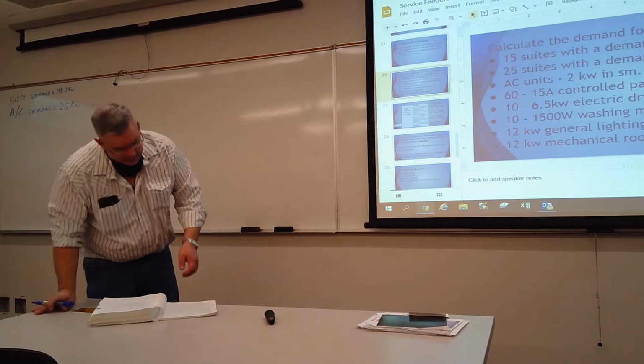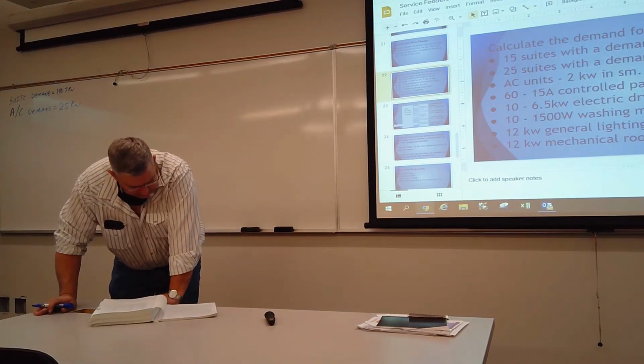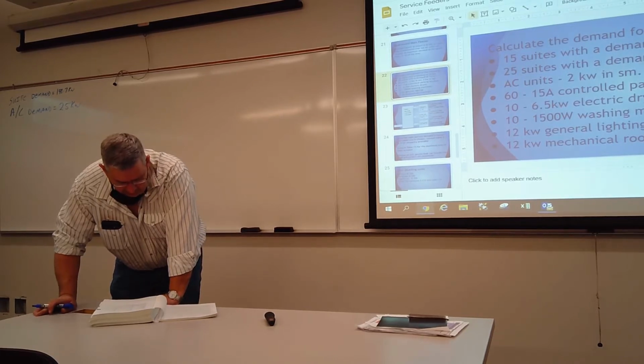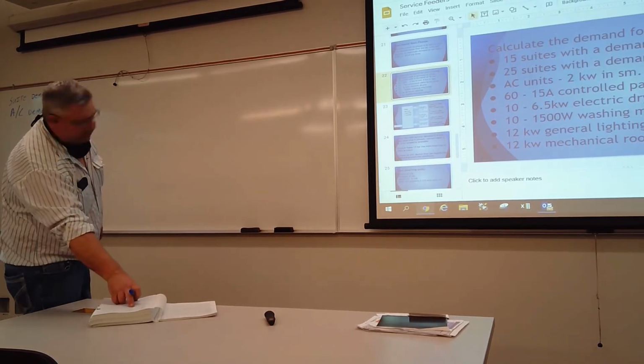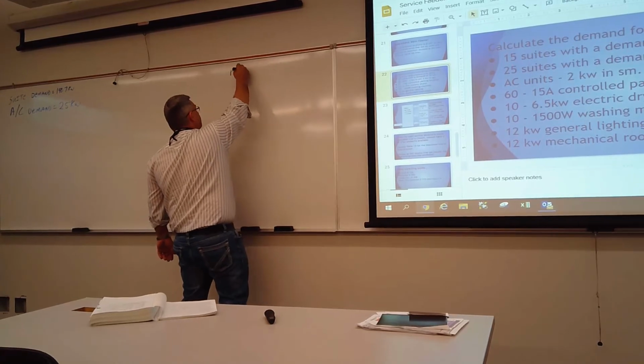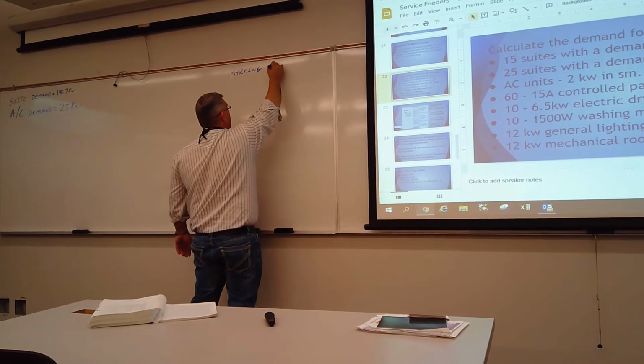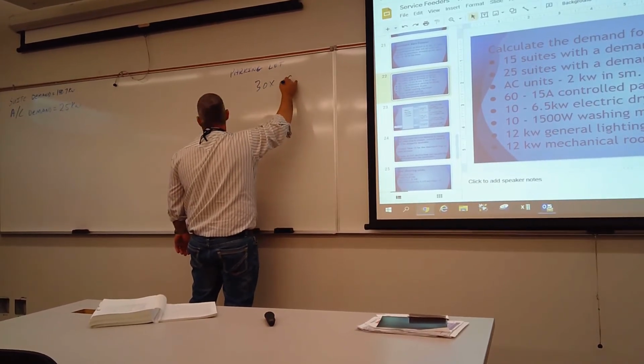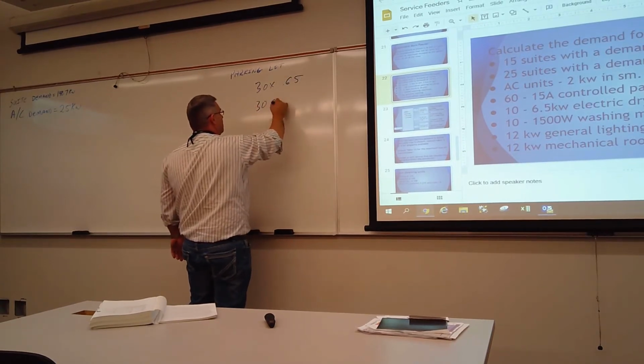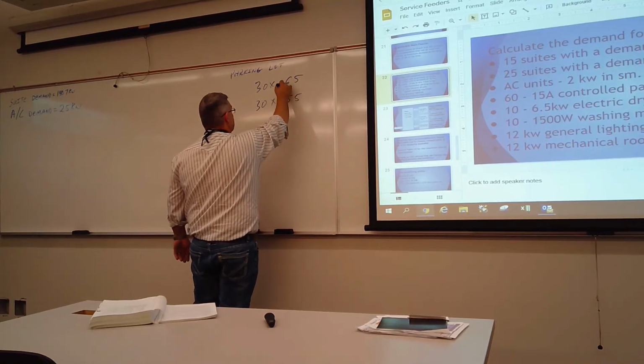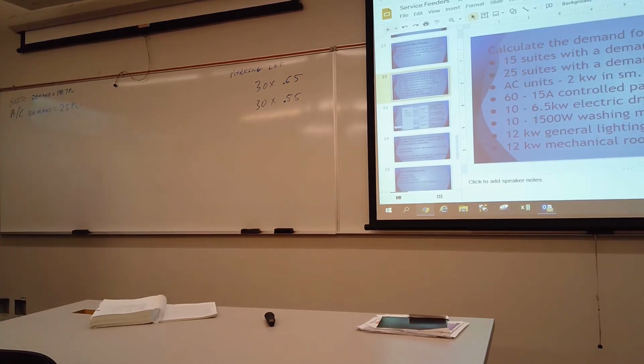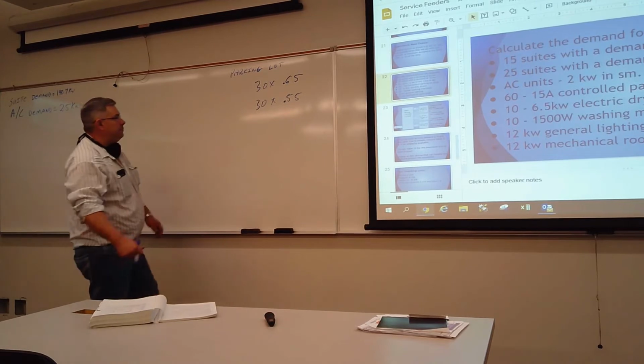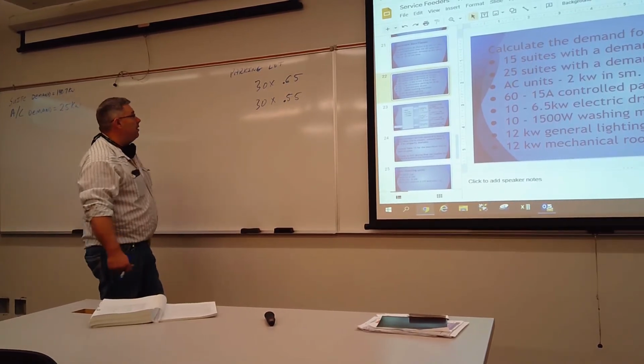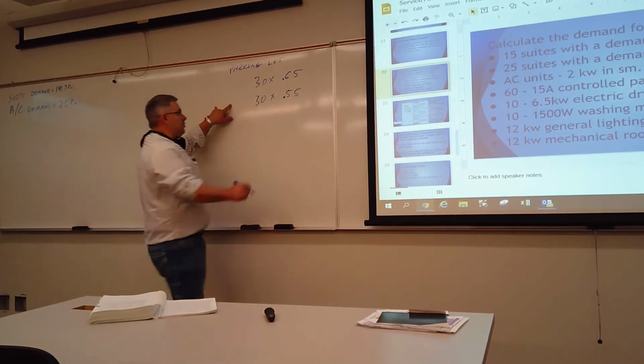We go to rule 8-400, sub-rule 4. If we're on a 15 amp circuit, the first 30 have a demand of 650 watts apiece, and the next 30 have a demand of 550 watts apiece. So our parking plugs: 30 times 0.65 and 30 times 0.55. Because everything else is in kilowatts, we might as well put them in kilowatts as well. Make sure you do that, because if you add watts and kilowatts together at face value, it doesn't work very well. Be amazed how many times that actually happens. So the total is 36 kilowatts.